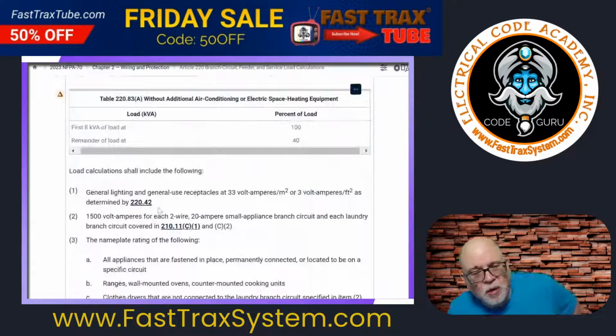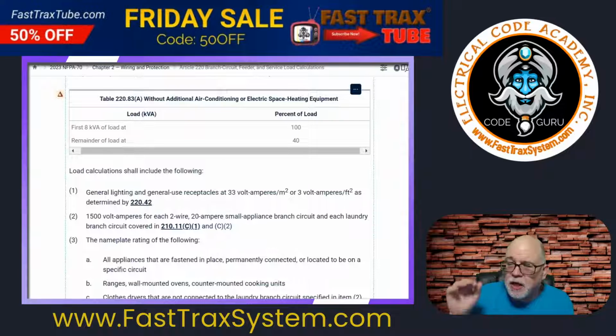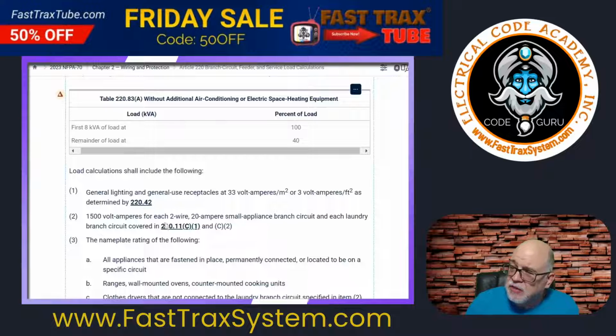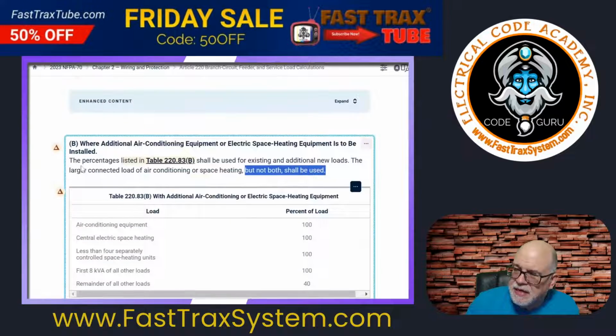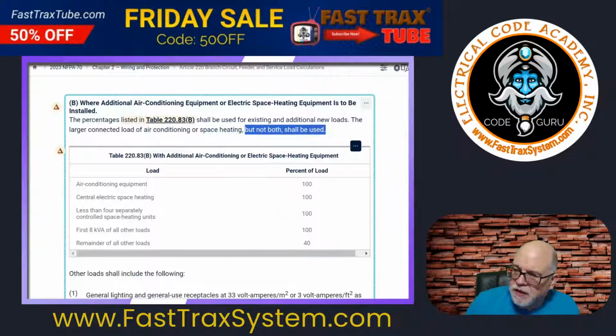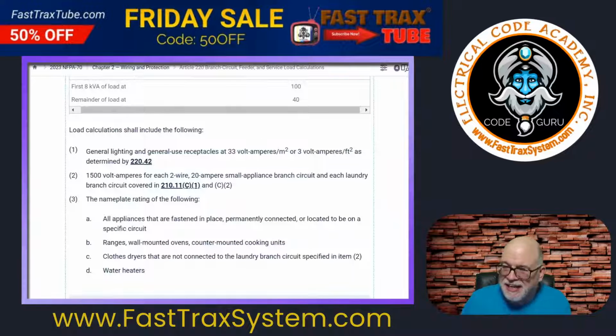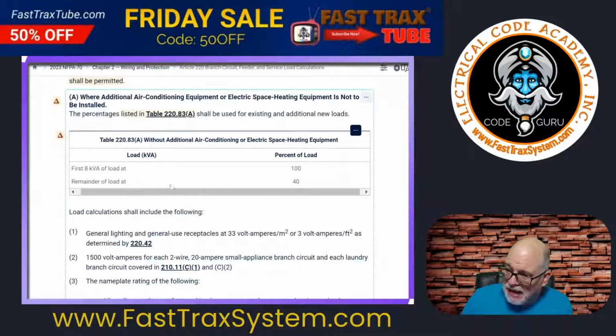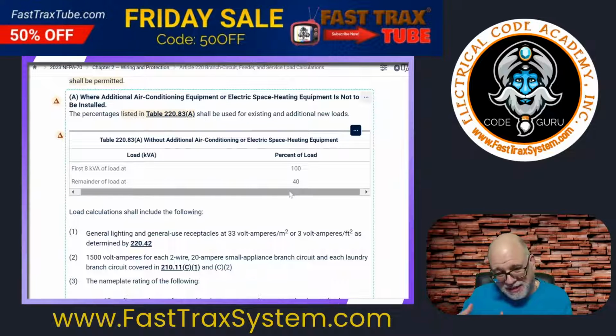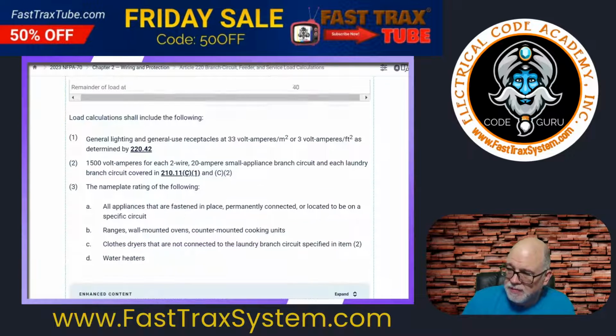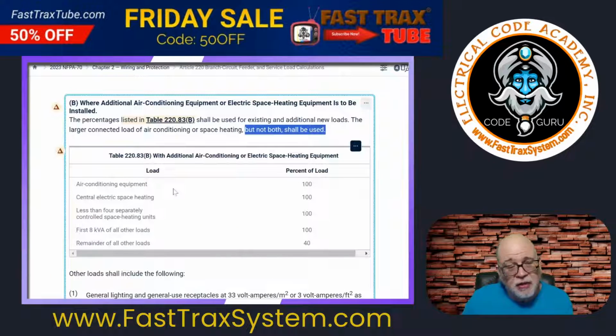Now, in the 2026 edition that's going to be coming out, the problem with A and B is that it's been argued that B would be a situation where if you were to wait until something is considered existing, then you're able to incorporate the air conditioning or the heating, whichever's larger, into this method A, and you get to apply the 40% to it. So you're going to get a greater demand than if you went down here and added additional air conditioning loads over and above what was already there. Then you have to take those new ones at 100%.